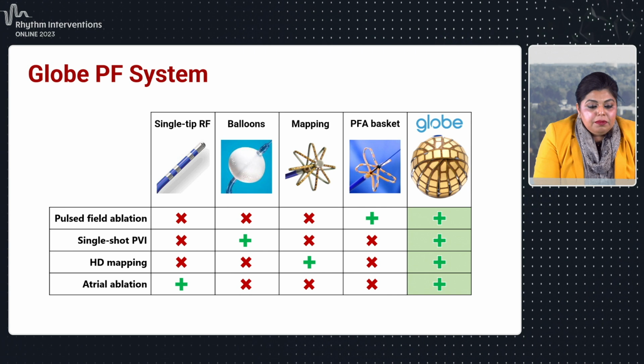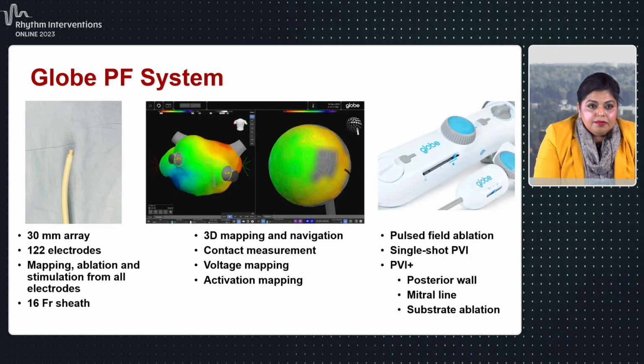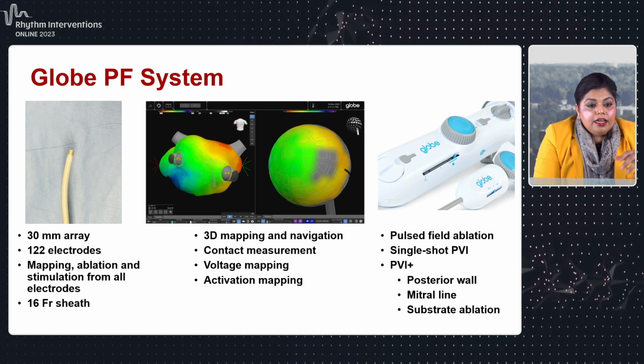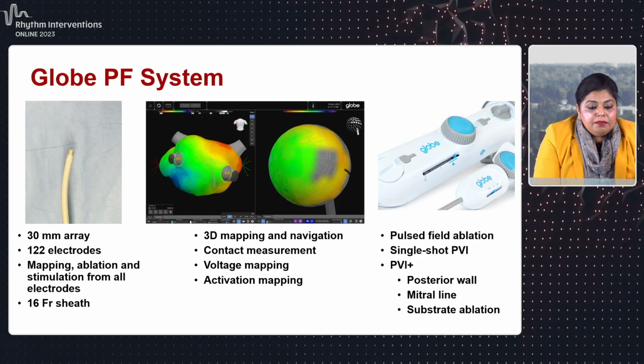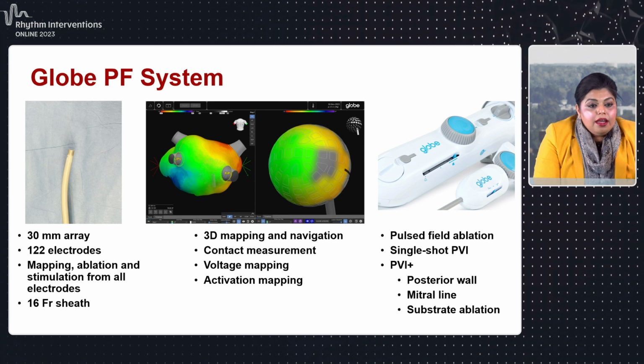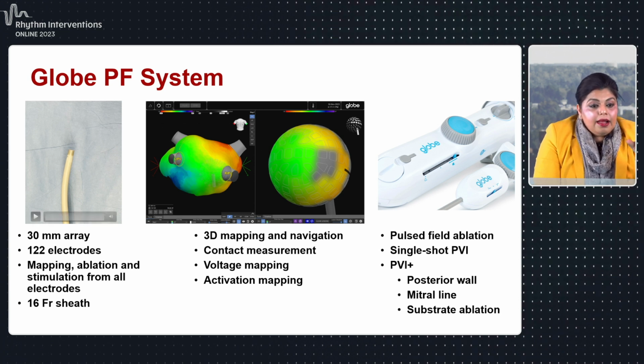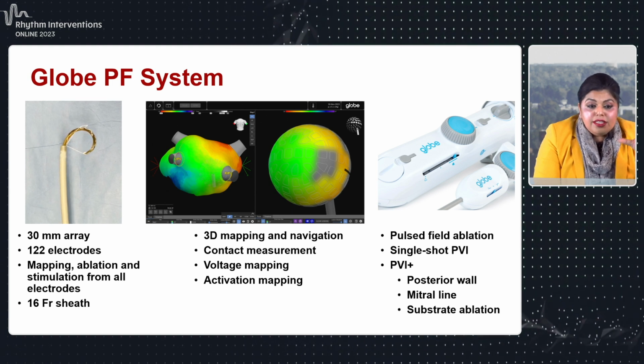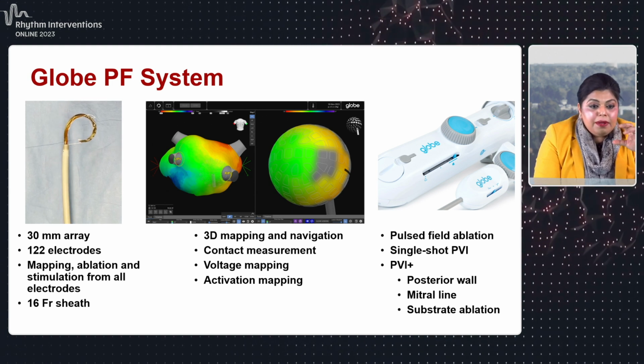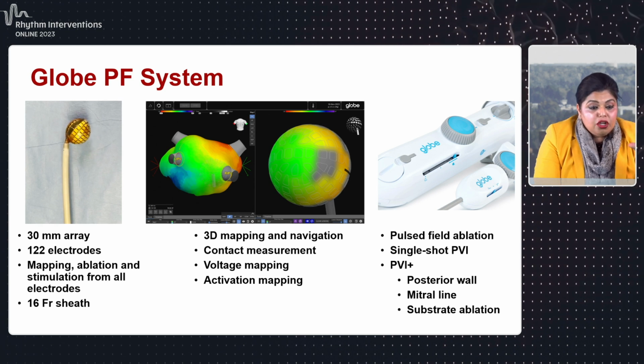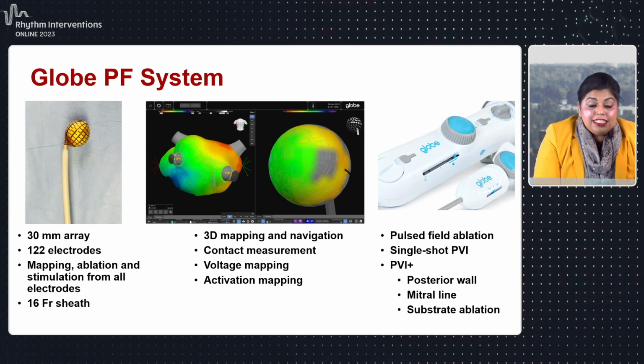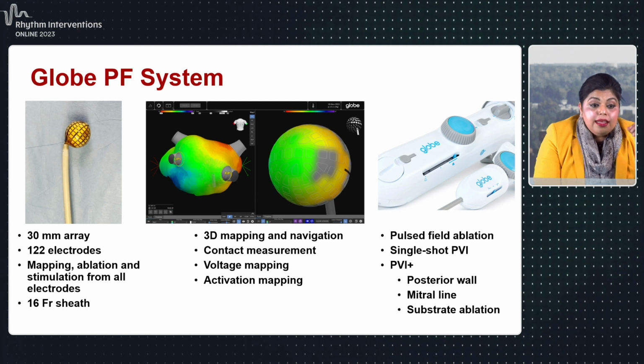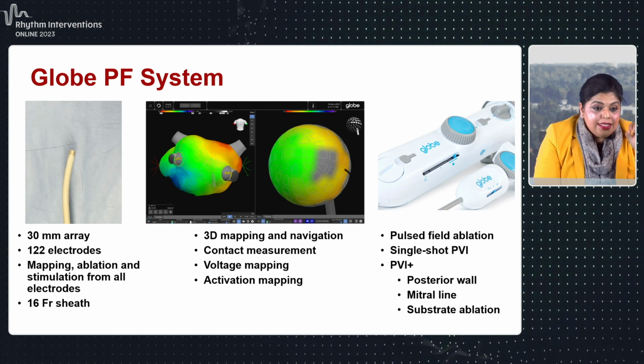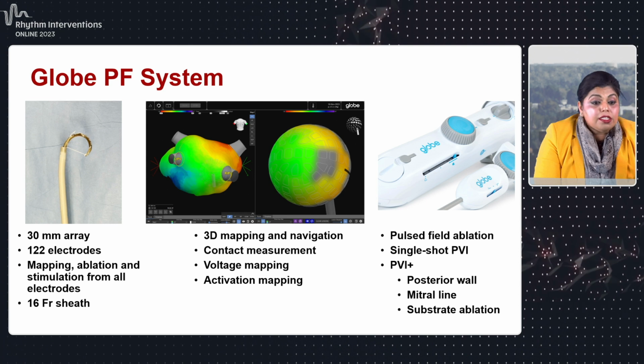Can you advance that slide for me, please? Thank you. So the system as such is a 30 millimeter array that, let me just go back there, sorry. And if you can play that video, that'd be great. It's a 30 millimeter array that has about 122 electrodes. Each of these electrodes are about 3 to 4 millimeters and about 1 to 2 millimeters apart from each other. It is introduced through a 16 French sheath. That's the inner diameter of the sheath. Each of these electrodes is able to map, it's able to pace, and it's also able to ablate.